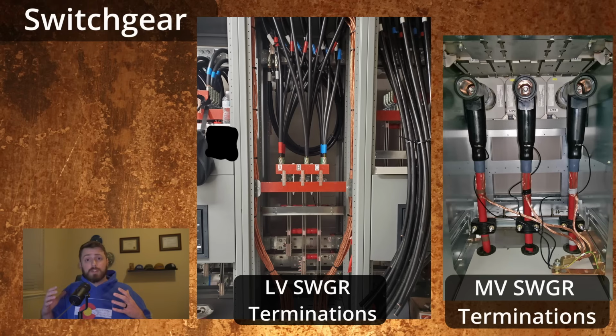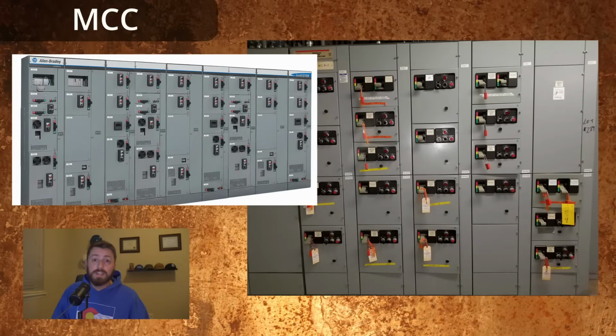On medium voltage switchgear, oftentimes the cables come into their own completely separate section. So you've got a cable termination enclosure at the rear of the switchgear, which is completely separated from any bus. The other honorable mention here is MCCs, or motor control centers, which share characteristics with both switchgear and switchboards, but they're their own distinct thing.